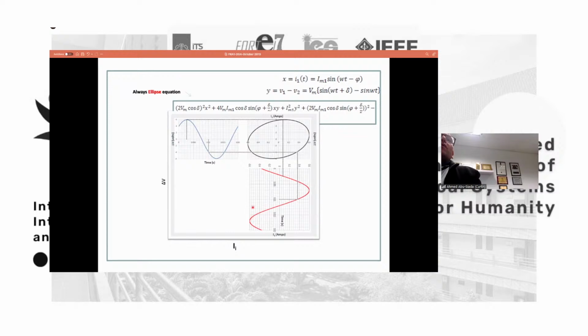Mathematically, that will be an ellipse. So when I plot the voltage difference of each phase against input current, it will be an ellipse like that. My thought was, can I use this ellipse as the fingerprint for each phase? And if I have any deviation from this, either a bigger area or a rotated ellipse, can that be an indication of a fault? So that's a graphical illustration of the technique, very simple. All I want to do is measure the difference of the voltage against the input current. So for each cycle, I will detect the current and voltage and plot the ellipse in 20 milliseconds.